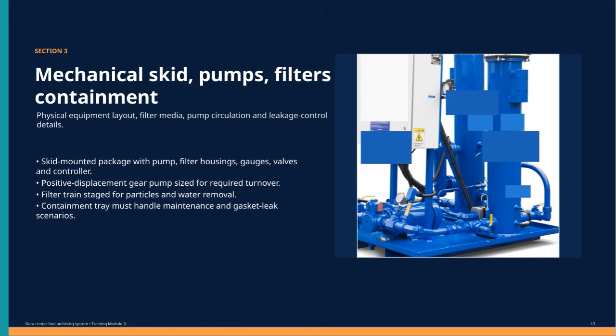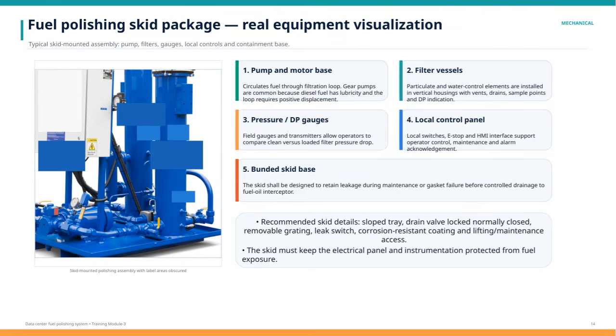Here we have a real equipment visualization of a fuel polishing skid package, which is a typical skid-mounted assembly. This system includes several key components such as the pump, filters, gauges, local controls, and a containment base, all mounted together for efficient fuel treatment. Starting with the pump and motor base, this circulates fuel through the filtration loop. Gear pumps are commonly used because diesel fuel provides lubrication and positive displacement is necessary to maintain consistent flow in the loop. Next, the filter vessels play a crucial role.